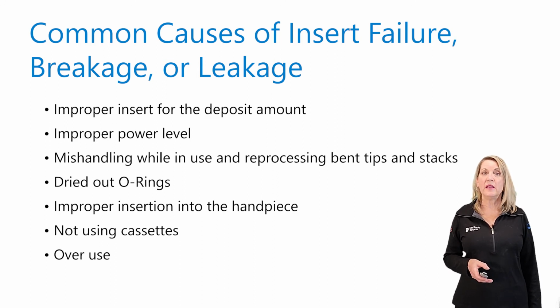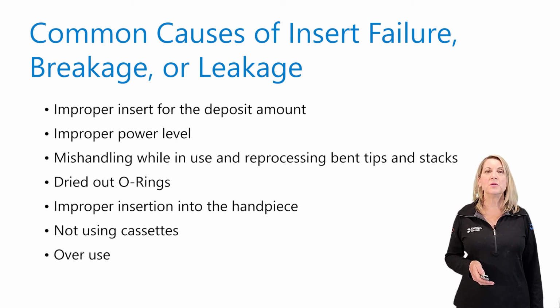When reprocessing, handle the inserts with care. We recommend a cassette to protect the inserts while being reprocessed. If the tip is bent or the stack is warped, then the insert must be discarded. They cannot be reshaped or unbent. Do not use disinfecting wipes on the inserts, as it will dry out the O-rings and cause the inserts to leak. Follow the proper reprocessing instructions, which can be reviewed in the next slide.